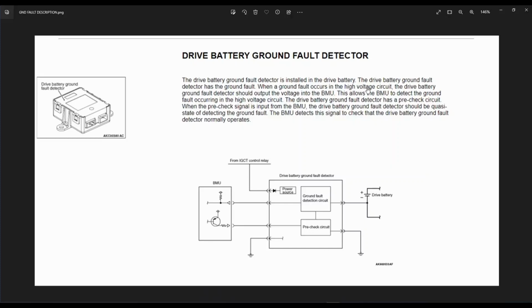Now, when a ground fault occurs in the high voltage circuit, so whenever there is a short to ground, chassis ground, in this system here, the drive battery fault detector should output the voltage into the BMU, battery monitoring unit, which is separate from the battery. So this device is inside the battery, this side is outside, right hand rear quarter panel. Okay, so here's our sense circuit, and that is our pre-check circuit. Initially what it's asking us to do is continuity check and short circuit test these wires here.